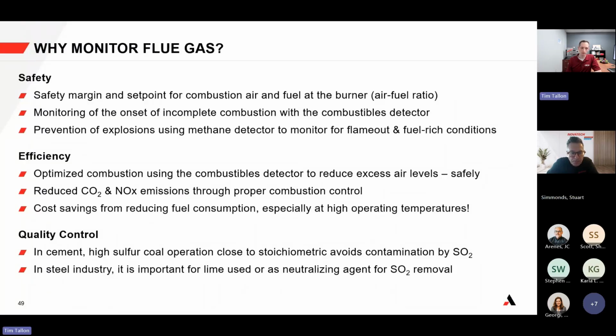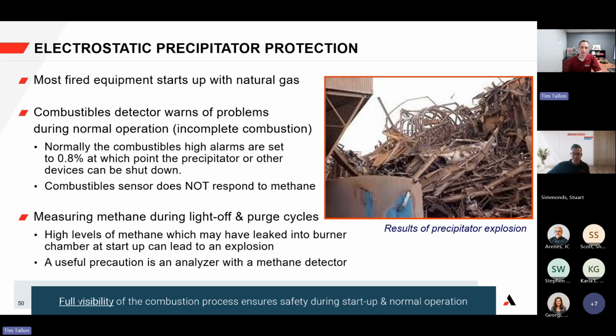One example is a high particulate application like an electrostatic precipitator, where having full visibility of the combustion process matters. A lot of equipment starts up on natural gas, and a combustible measurement analyzer won't see methane. So a combustible detector helps for normal operation, but it won't respond to methane. Having a methane detector to monitor for light-off and purge cycles can protect downstream equipment from unsafe conditions. It's a precaution to monitor for flameout or ignition that hasn't been purged suitably. So it's about providing full visibility of the combustion process, seeing how excess oxygen, combustibles, and methane work together during startup and normal operation.